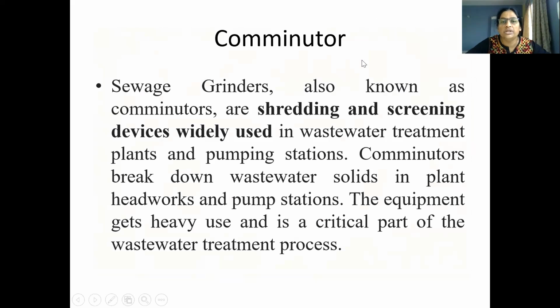So the next one is the comminutor. What is the function of a comminutor? Usually it converts the screenings, the larger size particles like leaves of plants and papers, into small pieces. In screening we remove such material and treat it separately. But in a comminutor, we crush it into small pieces and allow it to flow along with the water. This is organic material and will become food for the microorganisms, which will decompose it along with the other organic material.